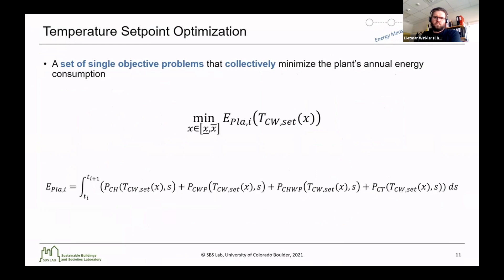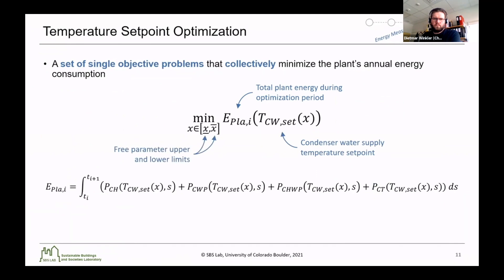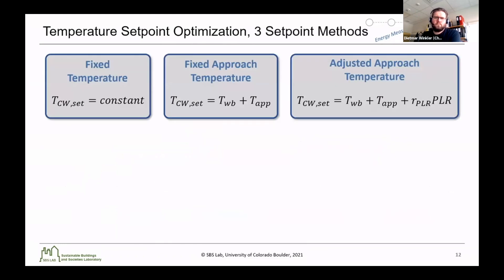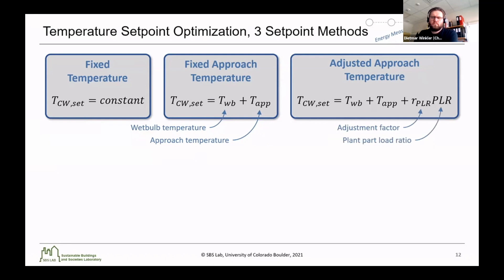For the temperature setpoint optimization, we formulated a set of single-objective problems that collectively minimize the plant's annual energy consumption. We looked to minimize the total plant energy during the optimization period by adjusting the condenser water supply temperature setpoint, constrained by the free parameter upper and lower limits. To calculate total plant energy, we integrated over the optimization time horizon the power of the chillers, the condenser water pumps, the chilled water pumps, and the cooling towers. We formulated three different setpoint methods: first, a fixed temperature where the condenser water supply temperature setpoint is a constant value; next, a fixed approach temperature where the setpoint is offset from the wet bulb temperature by a constant approach temperature; and thirdly, an adjusted approach temperature where the approach relative to the wet bulb is adjusted by some adjustment factor R relative to the plant's part load ratio.